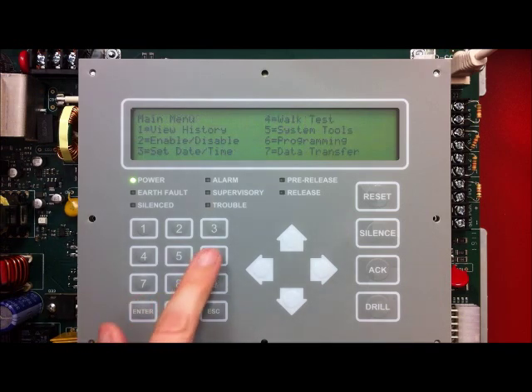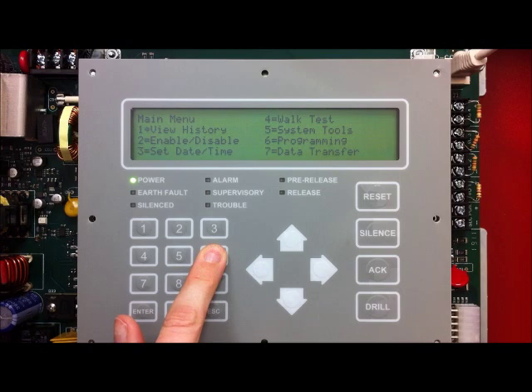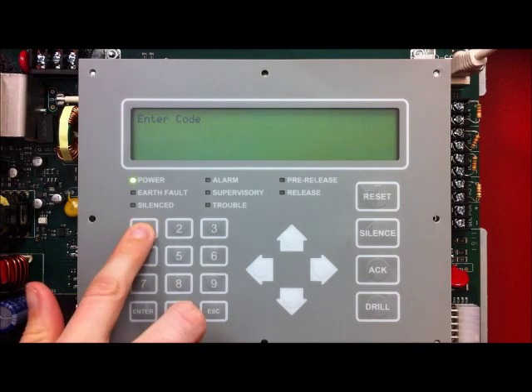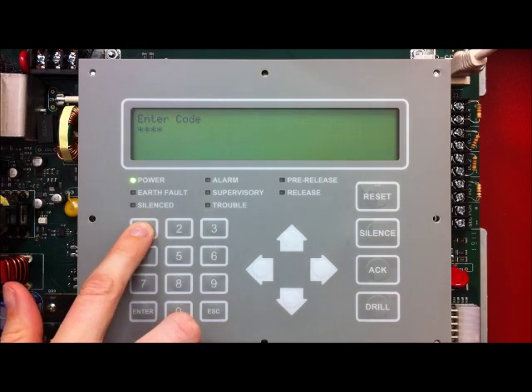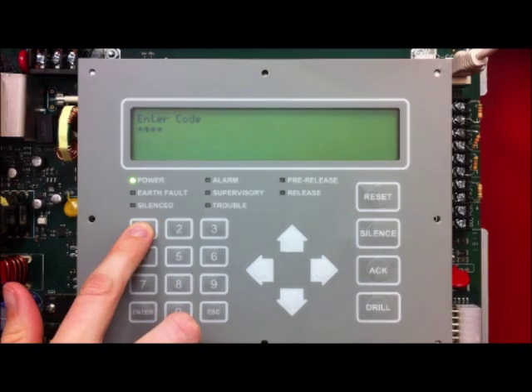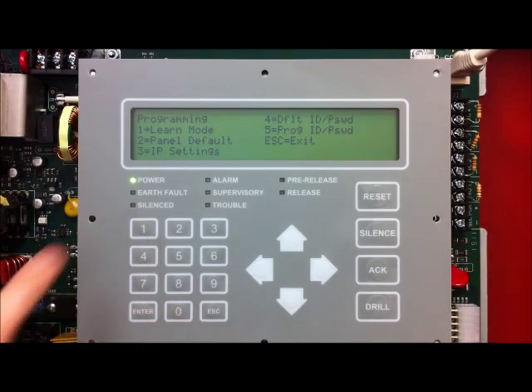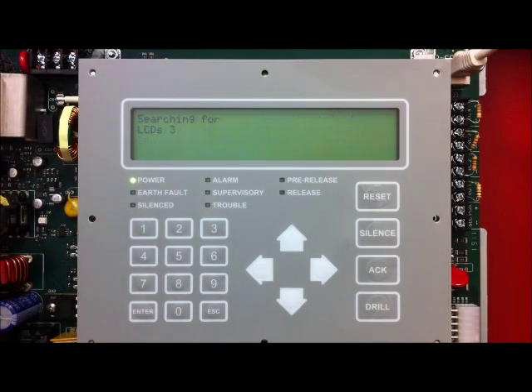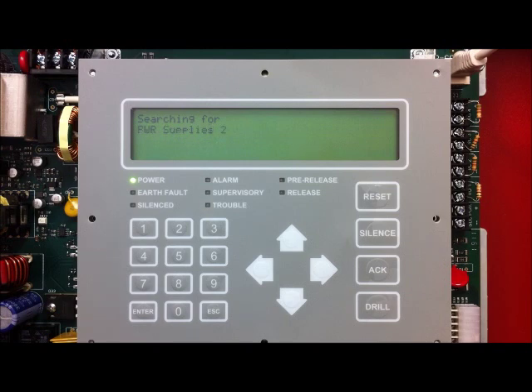Press ENTER to get into the main menu. In the main menu, press OPTION 6, Programming. You are then asked to enter a code. The default code from the factory is four 1s. Once in the programming menu, select OPTION 1, LEARN mode. LEARN mode is looking for all connected devices on the SLC and the PLINK bus. Once it is done, we can review it before accepting it.